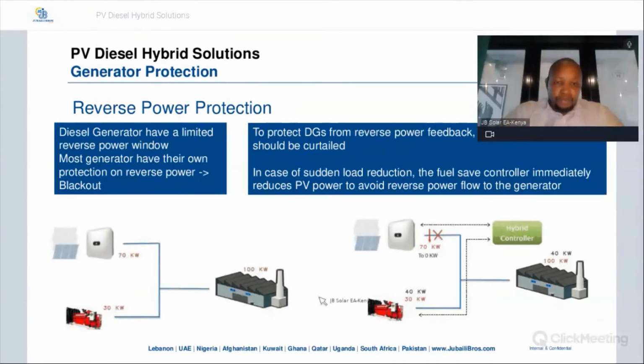As you can see from the images below, we have a load that is 100 kilowatts, and we're getting 70 kilowatts from the PV array and 30 kilowatts from the diesel generator. When the load drops to 40 kilowatts, we'll have excess power from the PV array that can be sent back to the diesel generator. However, with the hybrid controller, it can reduce or completely cut off the power coming from the PV side so that it does not flow back into the diesel generator. And so that is how the controller helps in reverse power protection.